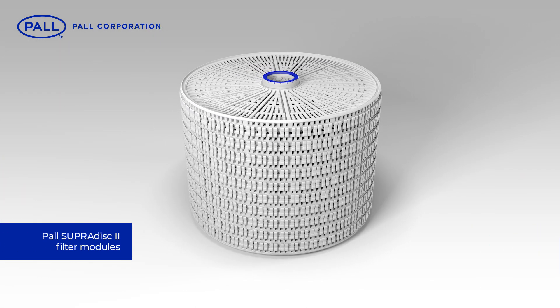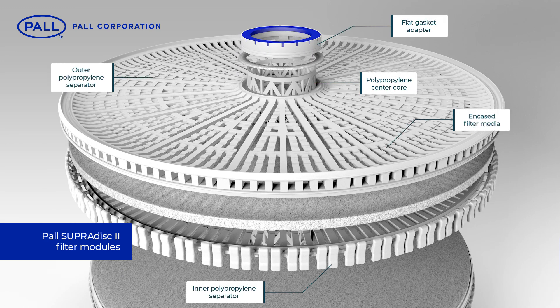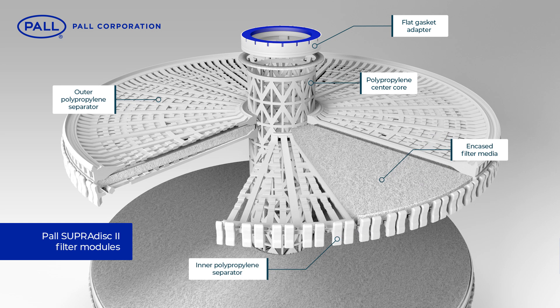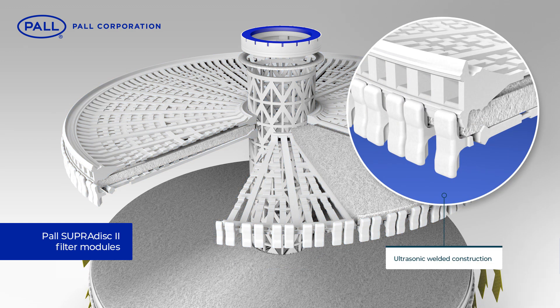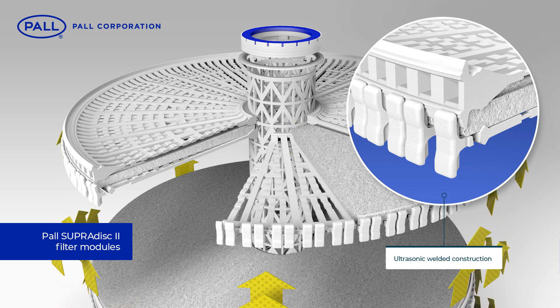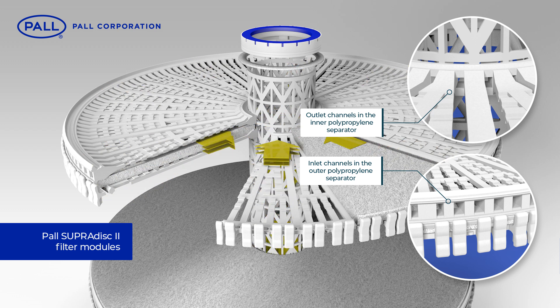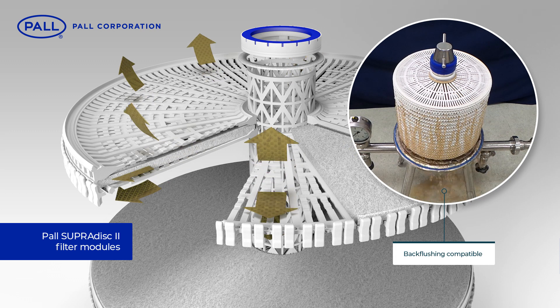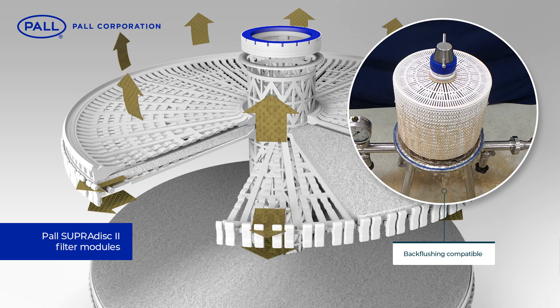The innovative design of the SUPRAdisc II modules decisively addresses these issues. By enclosing each filter cell in its own cage assembly, every media sheet is separated and supported by the rigid polypropylene structure. A bonding process using ultrasonic welding seals the outer edge, directing the flow of the filtrate through the designated separator channels. With both upstream and downstream support, the media resists deformation and cell collapse and back flushing of filter modules becomes possible.